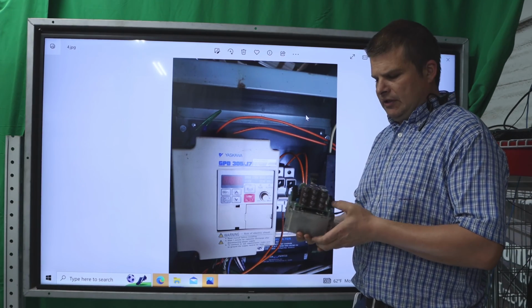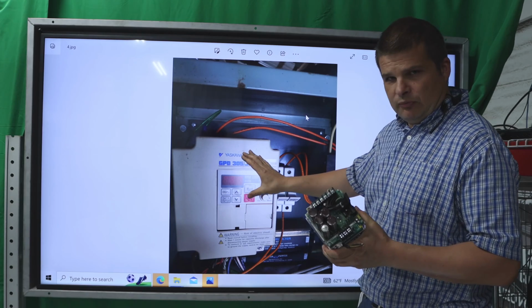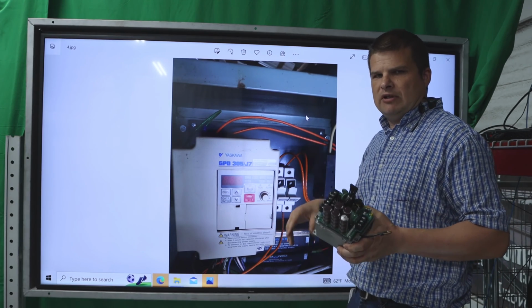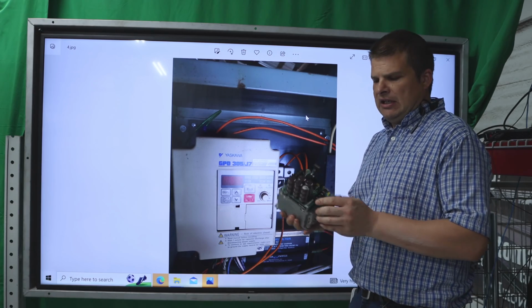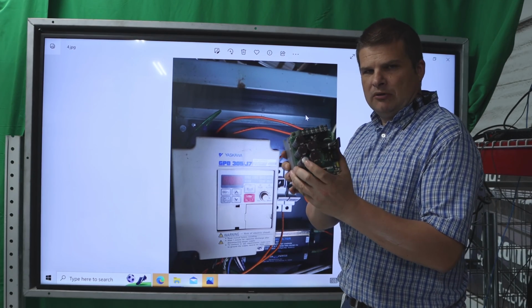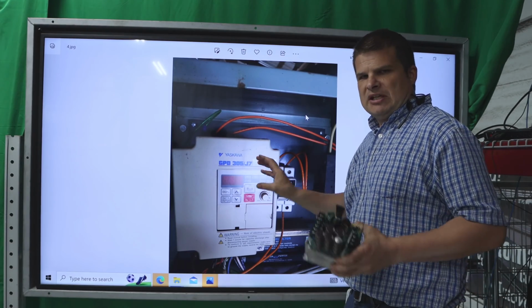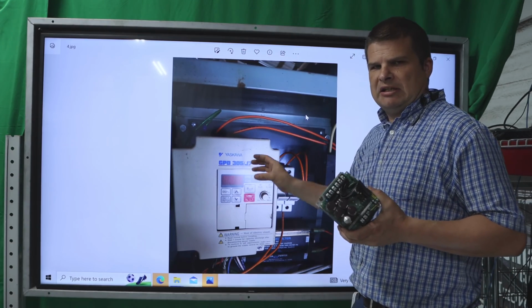And they're sensitive, and we just fixed one. There was an installation with three fans. They all quit running. We went out and checked things out, and here we found a bulged capacitor in the variable speed drive. We ended up replacing these with a different brand that are readily available.